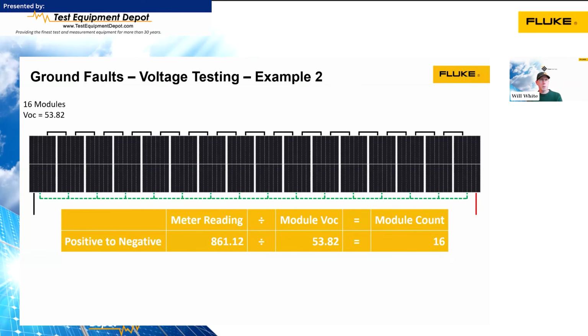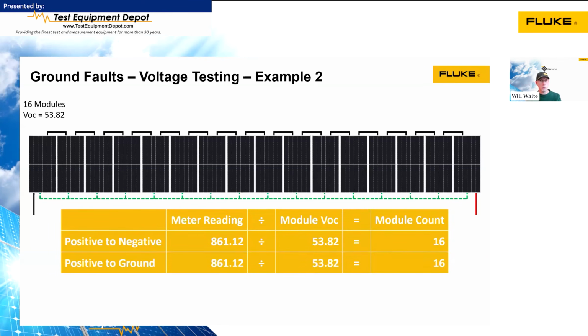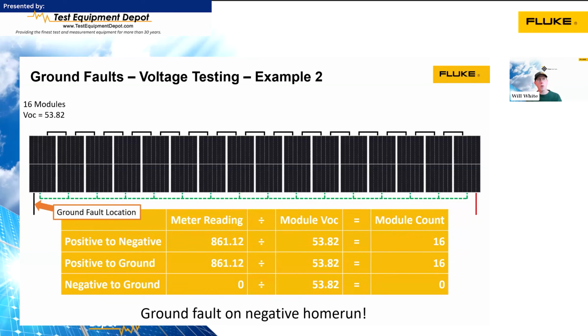Now, another example, and we'll go through this one a little quicker. Positive to negative, I got the same results as the last one, 16 modules in the string. Positive to ground, I got the same 861, so 16 modules. Negative to ground, I got 0, which is what I expected. What that tells me is there's 16 modules between the positive end and the ground fault, which would mean the ground fault is in the negative home run conductor.